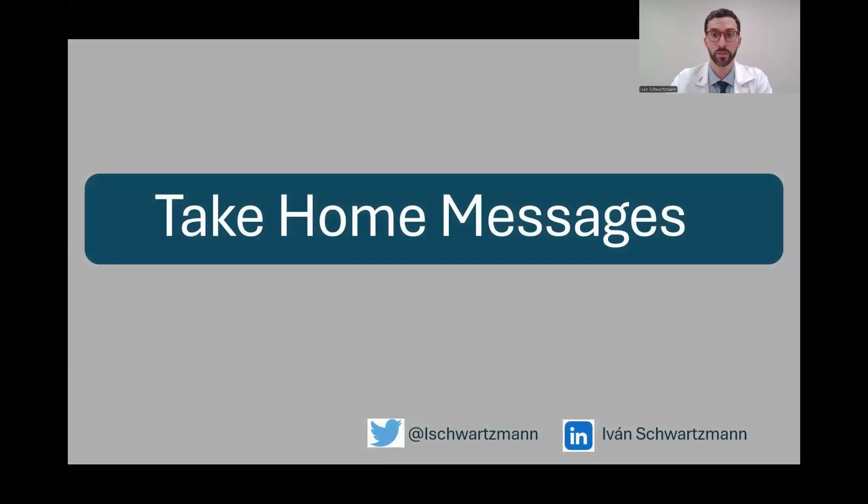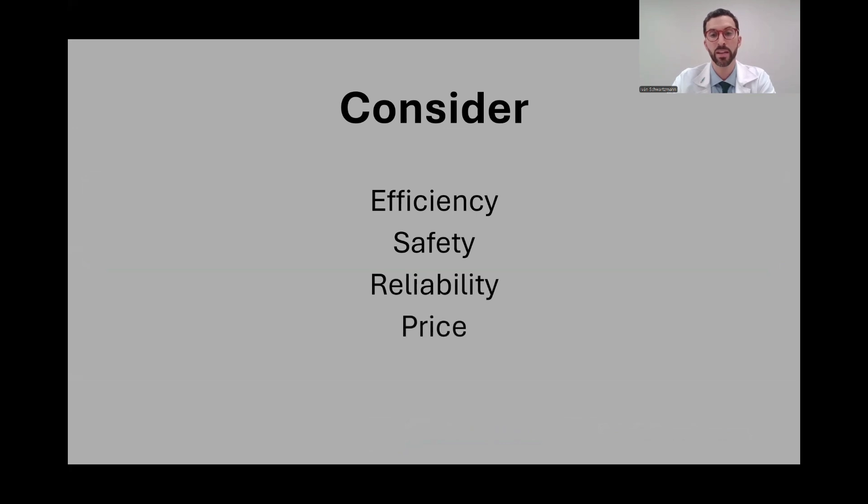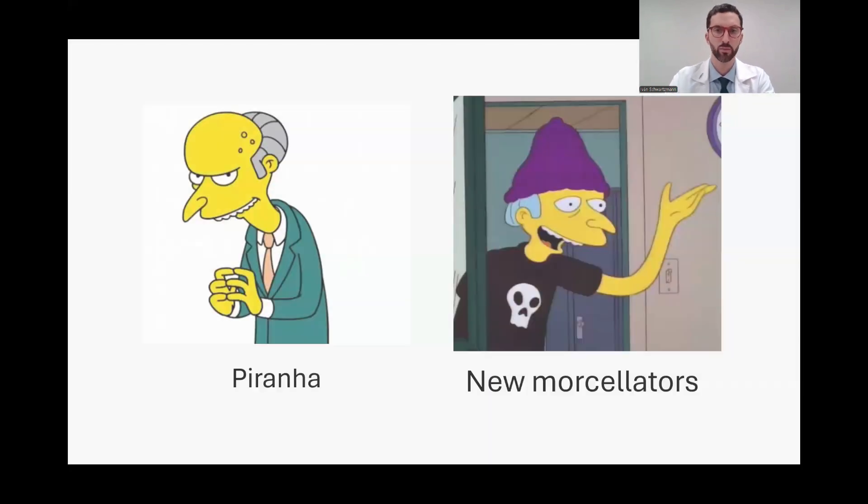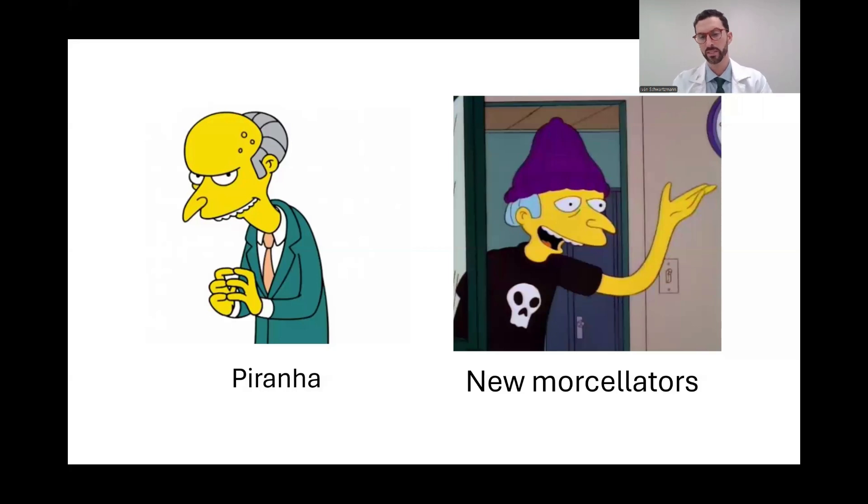Some quick take-home messages: when evaluating a morcellator, consider efficiency, safety, reliability, price, but also after-sales service. All new morcellators, except the Quanta Cyberblade, are essentially based on the Piranha design — there hasn't been a true revolution in morcellators yet. We hope there is one soon, because morcellation is something endoscopic enucleators are not big fans of — it's a bit dangerous and a bit too slow. Having said that, it is good to have competition and options in the market, as it makes the market more dynamic and benefits both patients and surgeons.